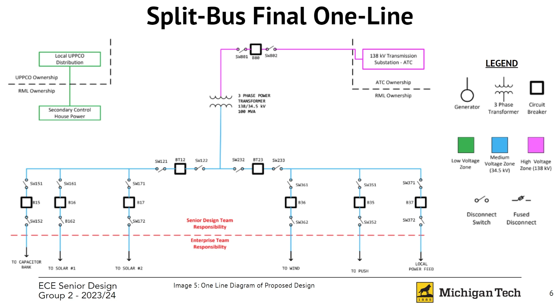Here's a one-line diagram of our design. At the top, the 138 kV transmission line comes into a 100 MVA transformer, which steps the voltage down to 34.5 kV. From there, it splits into two zones: one on the left for solar, and one on the right for pumped hydro, wind, and a local power feed.